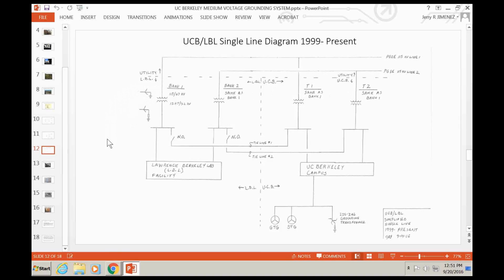I don't think that's recommended for 12 kV. You might get by with it at 480, but 12 kV, in my experience, every time somebody uses resistance grounding, it's going to be low resistance grounding. And yeah, you have to look at the current, but you have to look at what happens to the voltages as well. And with those high resistance grounding schemes, yeah, the 12 kV voltages to ground, I believe they can climb even higher than what they are with the low resistance grounded system. Those are for the phases that are unfaulted.